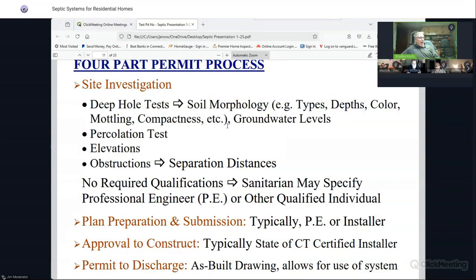And exemptions can be for a lot of things. It could be something as simple as this: for a residential system, you have to be 10 feet from the property line. If you're not 10 feet from the property line, it's considered a repair and they can give you an exemption. Now, obviously, the leaching trenches don't know where the property line is, so it doesn't necessarily make a difference in how the system functions.